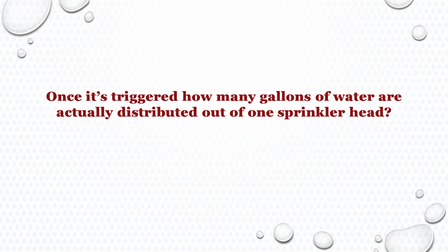So only the heads affected by the heat go off—it's not like the movies. The systems installed in this building have plates that drop at 135 degrees. Only the heads affected by heat discharge at about 155 degrees, releasing about 12 gallons per minute per head. Generally in a fire like that, in a building like this, you'd have just one head go off.